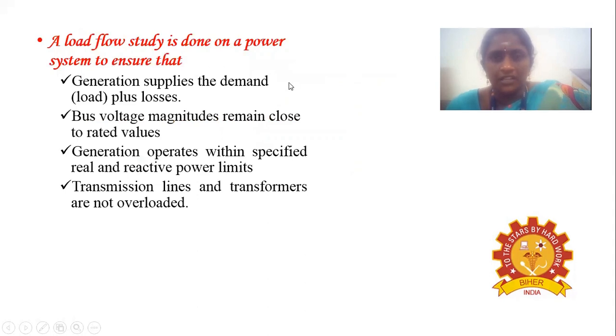Why we need to conduct the load flow studies: to ensure whether the generation supplies the demand plus losses, whether bus voltage magnitude remains close to rated value or not, whether the generation operates within the specified limit or not, and to check that the transmission lines and transformers are not overloaded.